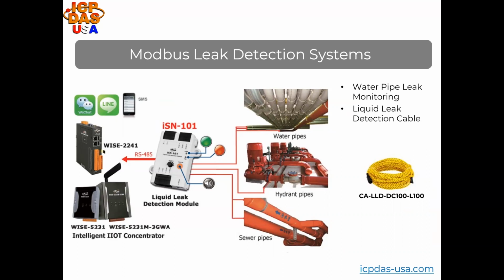The information is passed to the WISE IoT concentrators that have a logic rule engine for implementing control logic through if, then, else if type rule conditions that are configurable through a web page. ISN 101 has an audible alarm and a relay output that gets triggered if liquid is detected. So the water valves and the systems are shut off, and personnel is notified immediately through text messages, preventing further issues.